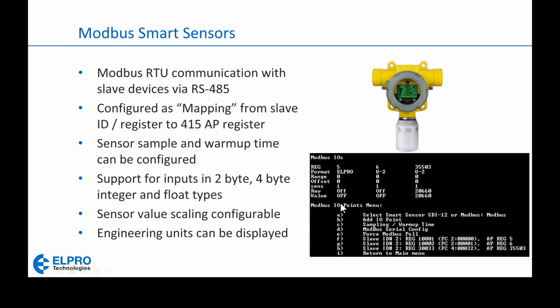Here we go. This kind of shows you the setup menu in your terminal program, how you would configure the whole thing. And of course, we can set the sample time and the warm-up time. So as I mentioned earlier, we could set the unit to have 10 seconds to power up and stabilize the reading. And then once that's finished, we can go ahead and take a sample and then remove power from the sensor to preserve the battery life.